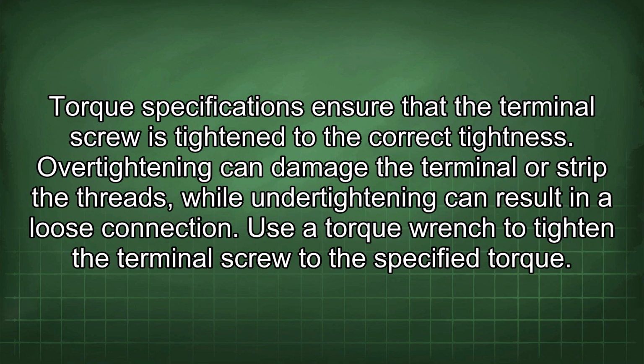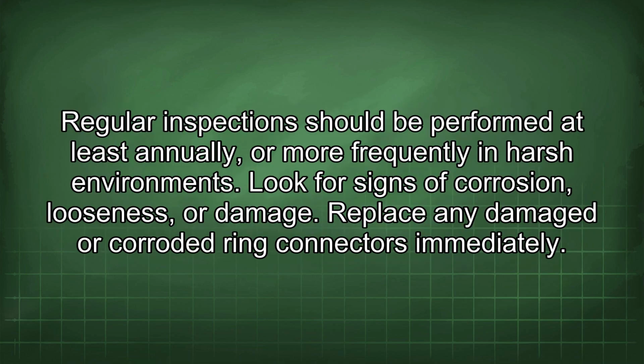Use a torque wrench to tighten the terminal screw to the specified torque. Regular inspection should be performed at least annually or more frequently in harsh environments. Look for signs of corrosion, looseness, or damage. Replace any damaged or corroded ring connectors immediately.